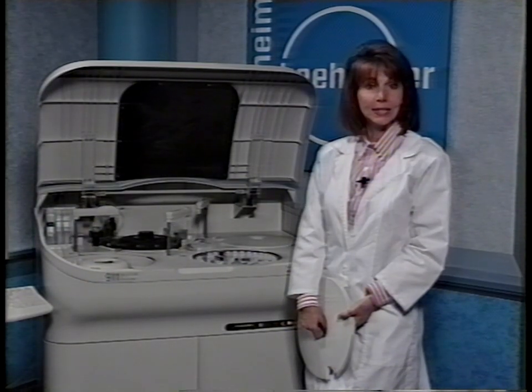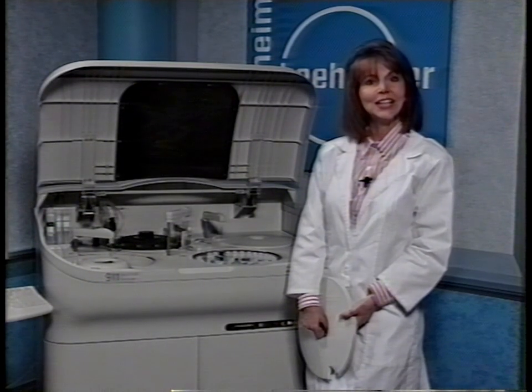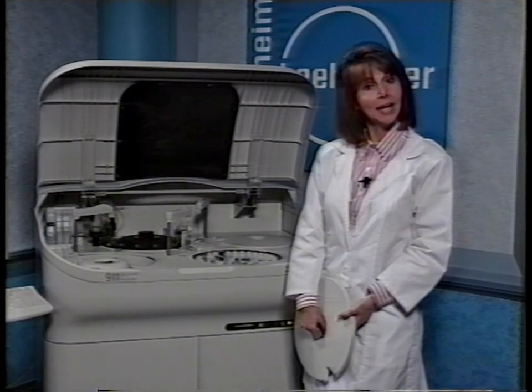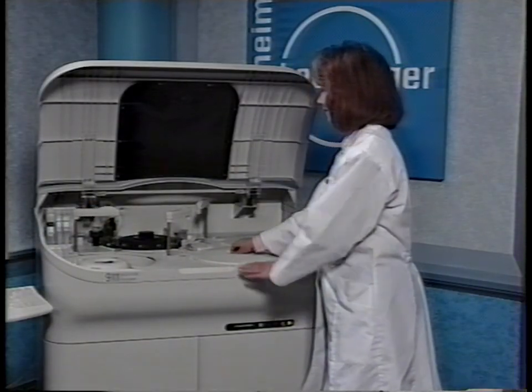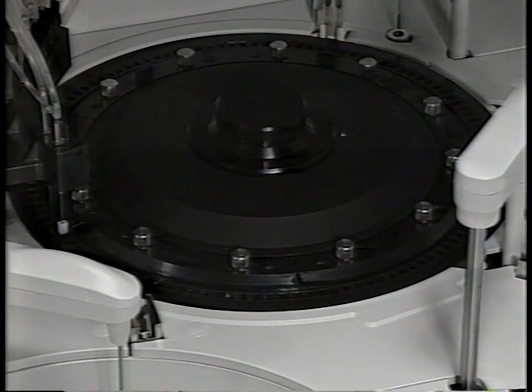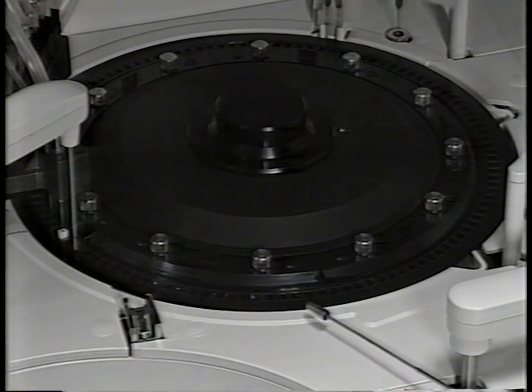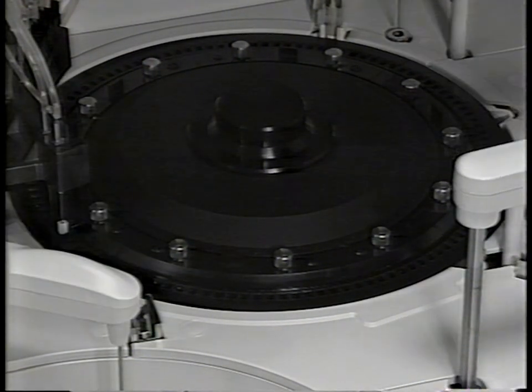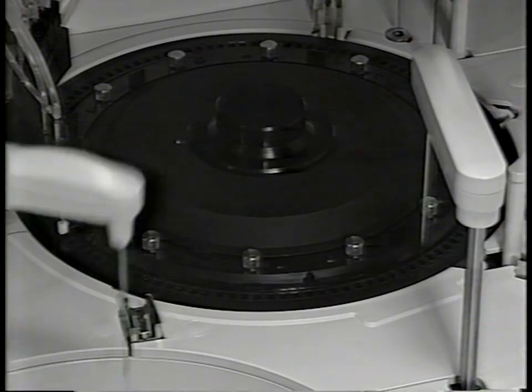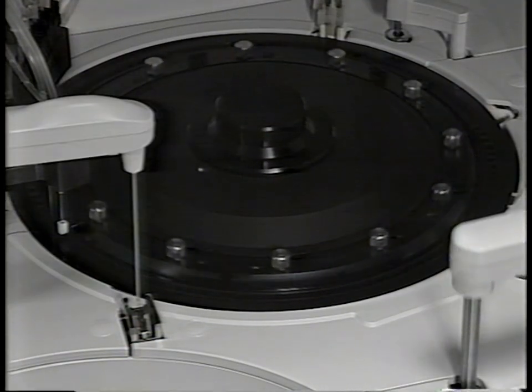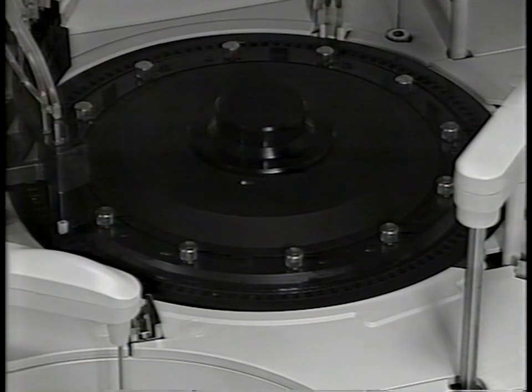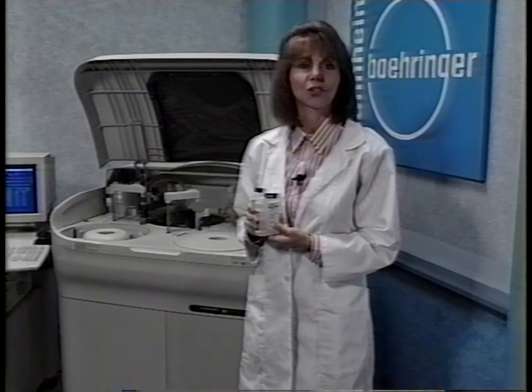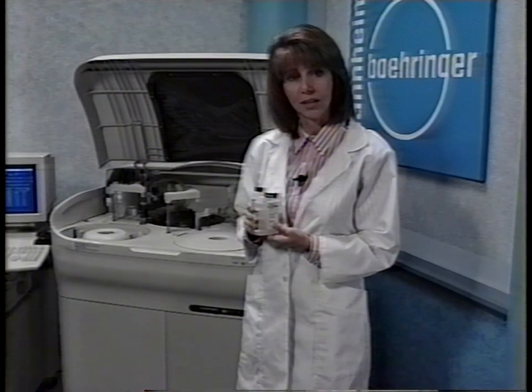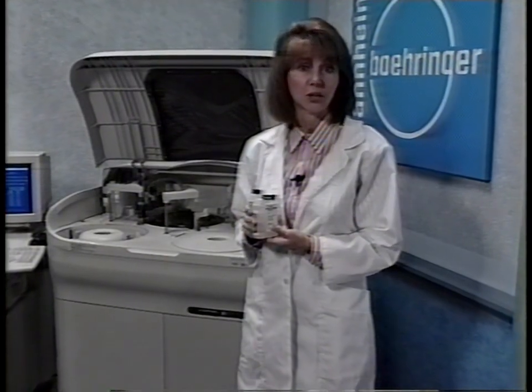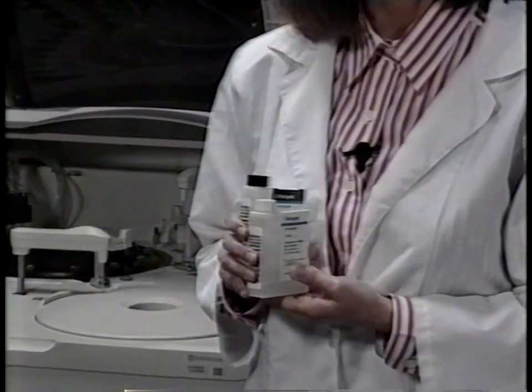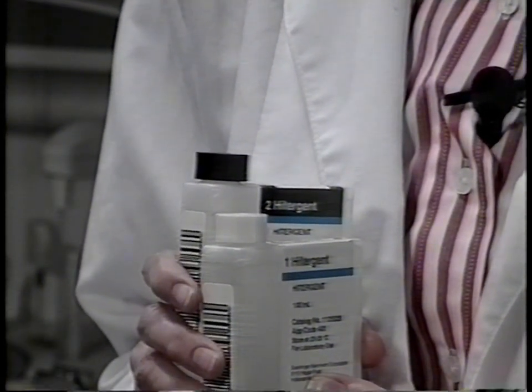Now that we've discussed the basics of the sample and reagent dispensing mechanisms, let's talk about the photometric measuring system, beginning with the reaction cells. The reaction disc has 120 reusable plastic cells around its perimeter. These reaction cells are suspended in an incubation water bath beneath the reaction disc. The bath maintains the cell reaction mixture at 37 degrees Celsius within 0.1 degree. A bacteriostatic surfactant called Hitergent is automatically added to the incubation bath by the reagent probes whenever the bath water is exchanged. Hitergent also prevents bubbles from adhering to the external optical surfaces of the reaction cells.